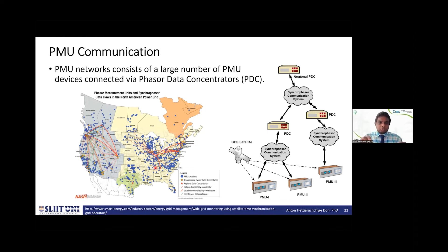For that map I showed you, this is what it looks like. The lines show how the networks are connected. You might ask why the blue side isn't connected to the yellow side. Actually, in the United States it's not one grid, we have 4 grids. They're connected through DC lines so frequency issues don't matter, but largely they operate on their own and don't have to be connected. So the 4 colors represent the 4 different networks in the North American region. On the blue side, the Pacific side with California and Nevada, everything is connected together, and each of these blue dots represents multiple PMUs connected.